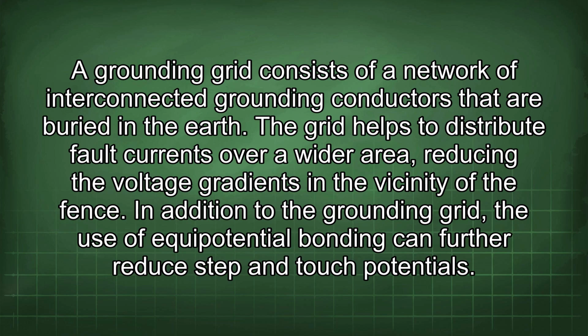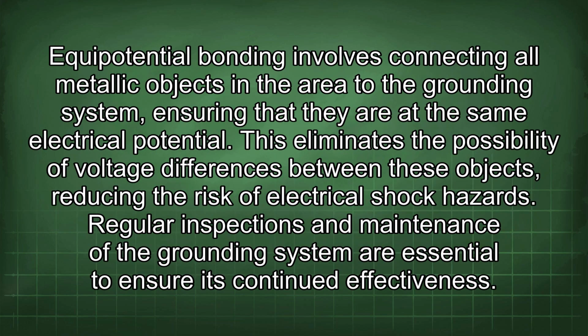A grounding grid consists of a network of interconnected grounding conductors that are buried in the earth. The grid helps to distribute fault currents over a wider area, reducing the voltage gradients in the vicinity of the fence. In addition to the grounding grid, the use of equipotential bonding can further reduce step and touch potentials. Equipotential bonding involves connecting all metallic objects in the area to the grounding system, ensuring that they are at the same electrical potential. This eliminates the possibility of voltage differences between these objects, reducing the risk of electrical shock hazards.